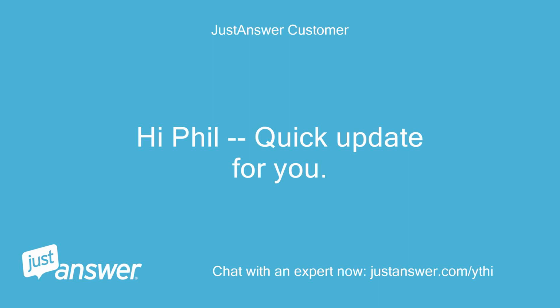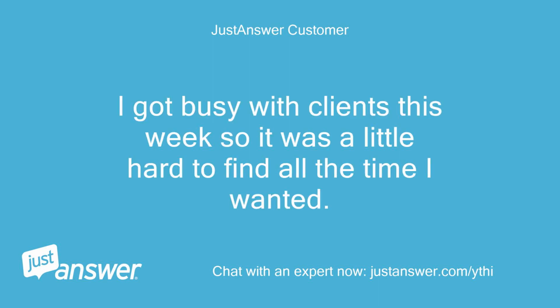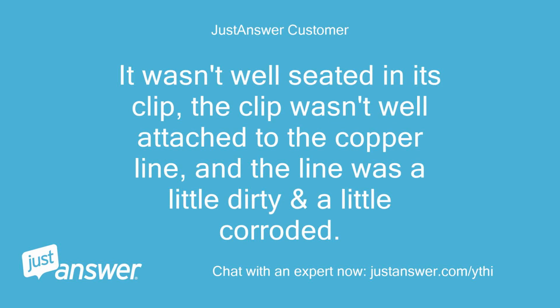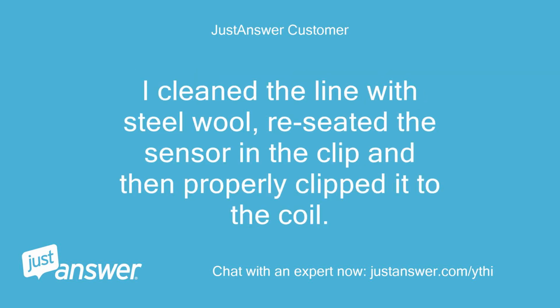Hi Phil, quick update for you. I got busy with clients this week, so it was a little hard to find all the time I wanted. Yesterday I did a more thorough inspection of the components in the outdoor unit and found that the coil temp sensor wasn't well attached to the coil. It wasn't well seated in its clip, the clip wasn't well attached to the copper line, and the line was a little dirty and a little corroded. I cleaned the line with steel wool, reseated the sensor in the clip and then properly clipped it to the coil.